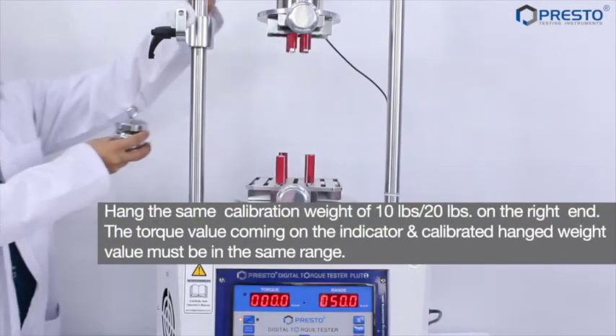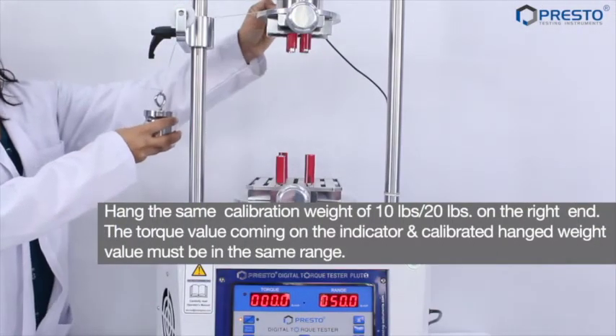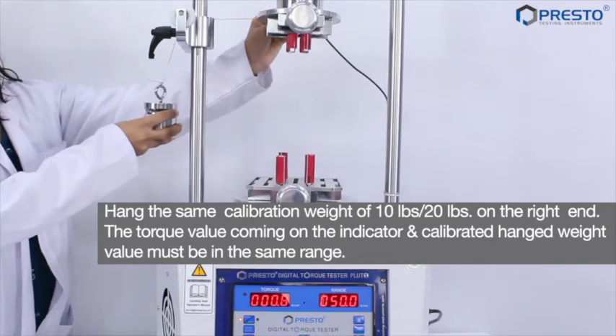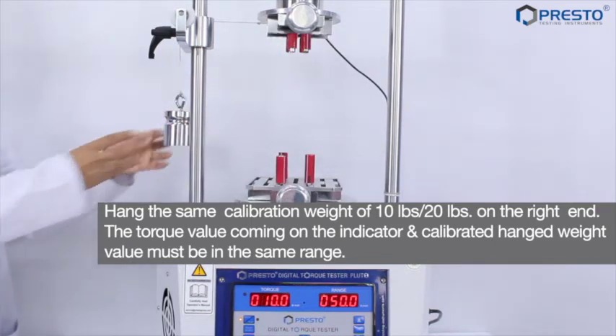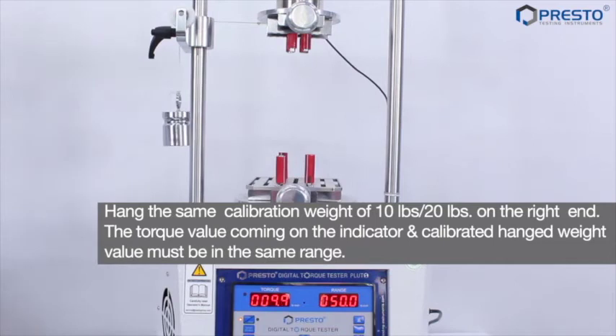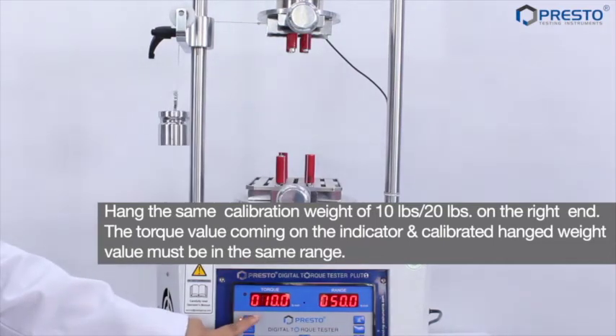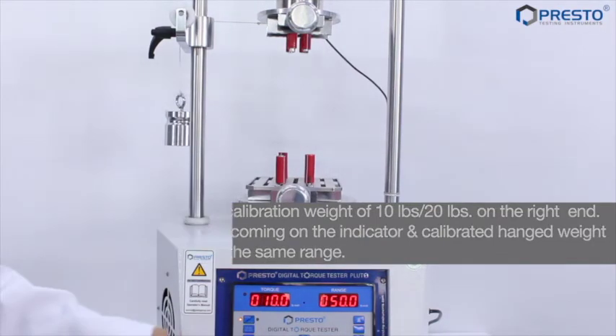Now hang the same calibrated weight of 10 lbs or 20 lbs on the right hand side. The torque value coming on the indicator and calibrated hang weight value must be in the same range.